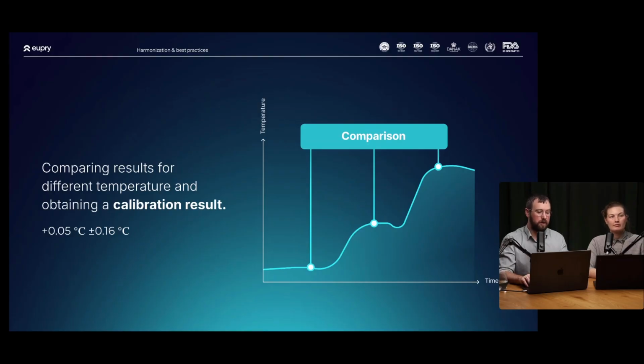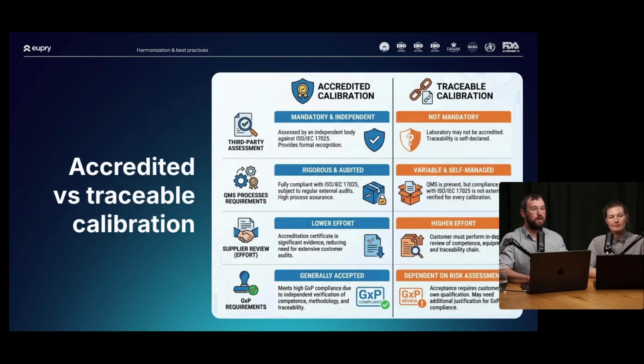So another part about calibration that we briefly discussed here is accredited versus traceable calibration. There's often a price difference between having accredited and traceable calibrations, but I think it's really important to mention that a traceable calibration is not necessarily worse than accredited calibration. What you do get, though, with an accredited calibration is that, first of all, there's a third-party assessment. When a company has an existing accreditation that has not expired, they have been assessed by an independent third party that has been appointed by that country's government. So it's not just any company that can go out and say, now we accredit companies against 17025. It's much more regulated than, let's say, 27001 or 9001.